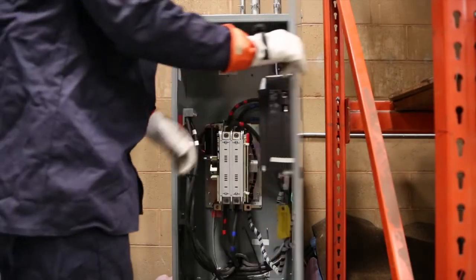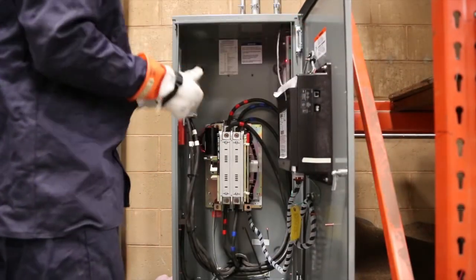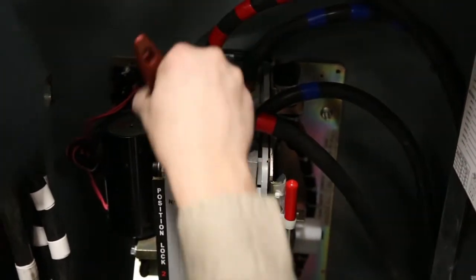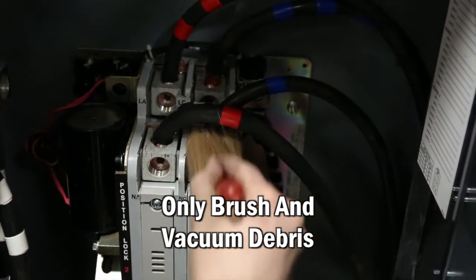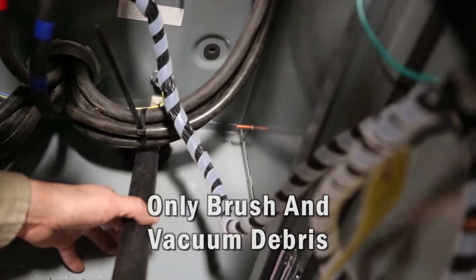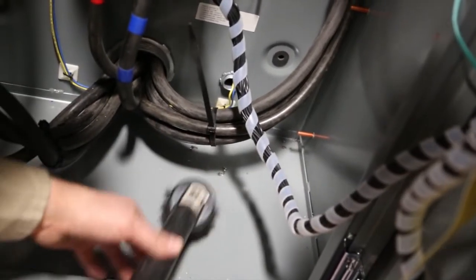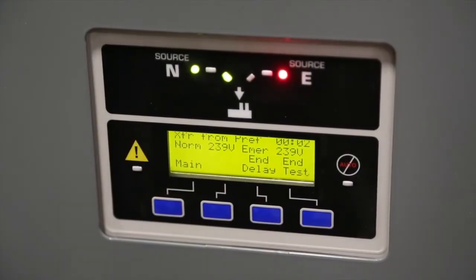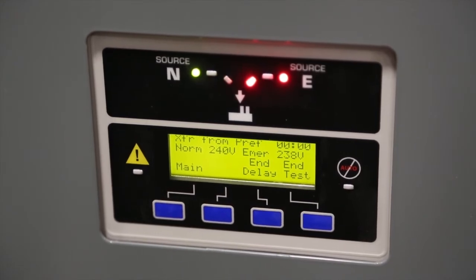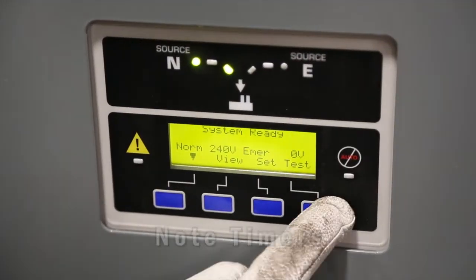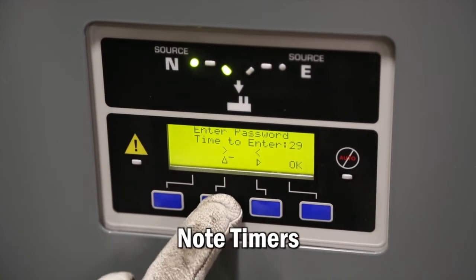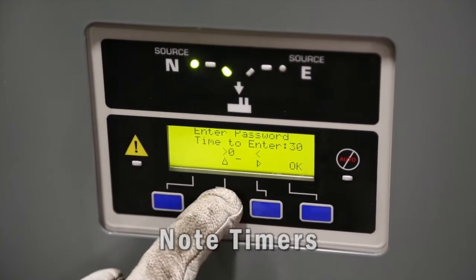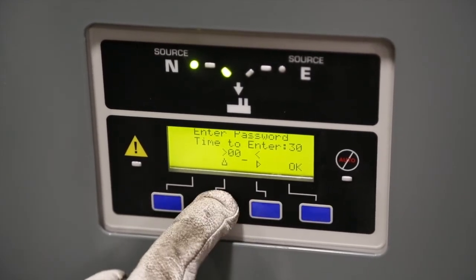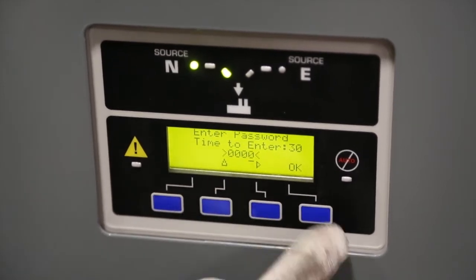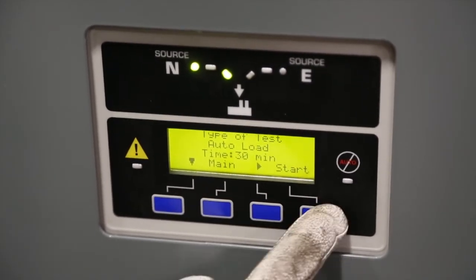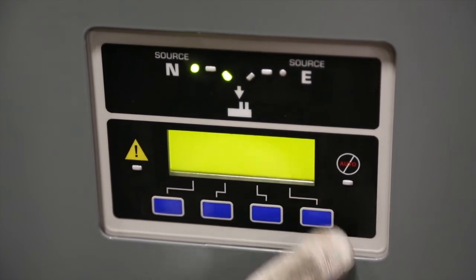During an ATS planned maintenance service call, the technician will brush and vacuum any dirt or debris from inside and outside of the ATS and never use compressed air to remove dirt or dust. Check the operation of the transfer switch before beginning service. Check timers controlling the time for transferring to the standby power supply and the time before returning power to the utility. This avoids several transfers when power is going on and off or only interrupted for a short period.